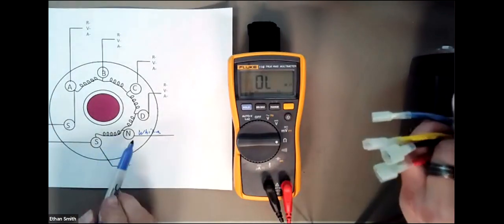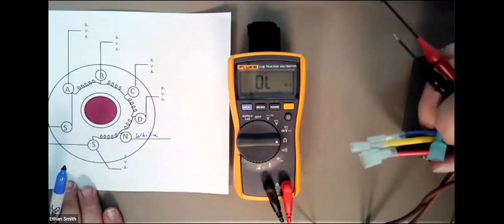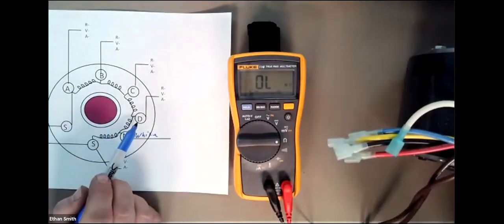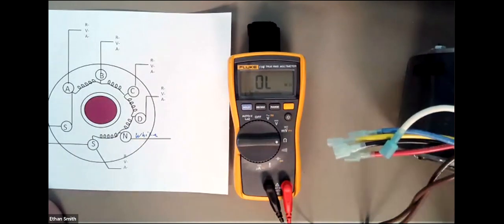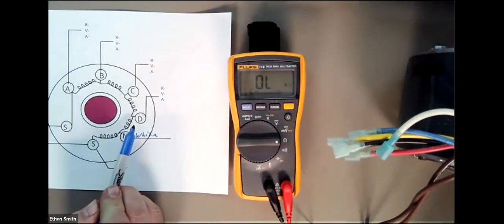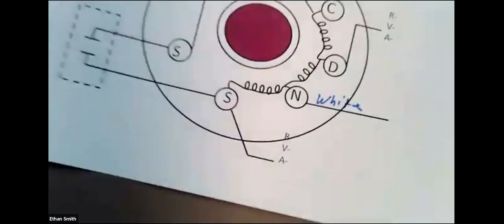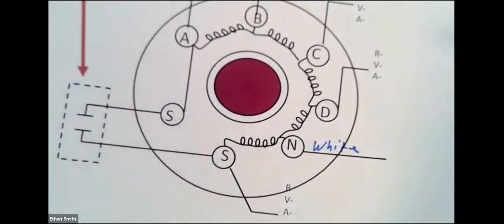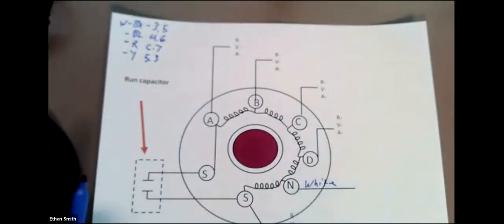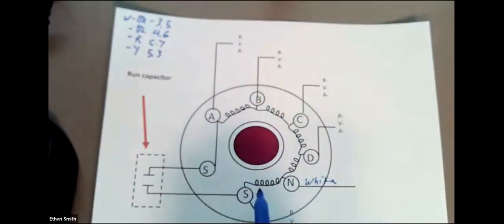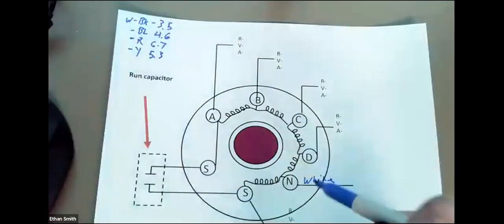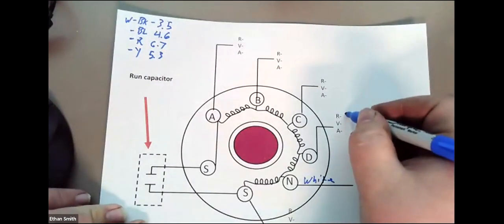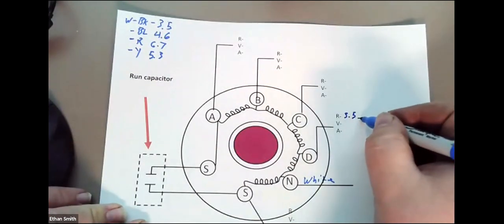Okay, so if you're looking at this motor, we know the white is neutral. So what color would D be? I've got terminal D right here. I'm going to zoom in so it's a little easier to see. Back it up just a little bit. So we've got all the resistance values. Would it be 3.5? Yeah, that's my lowest resistance, because that one's going to be closest to my neutral wire. So my resistance is 3.5 ohms.